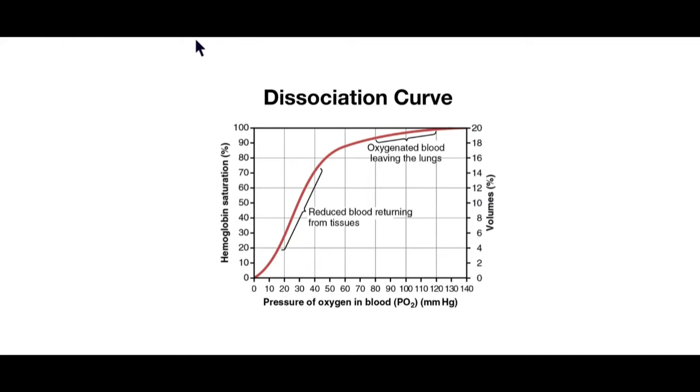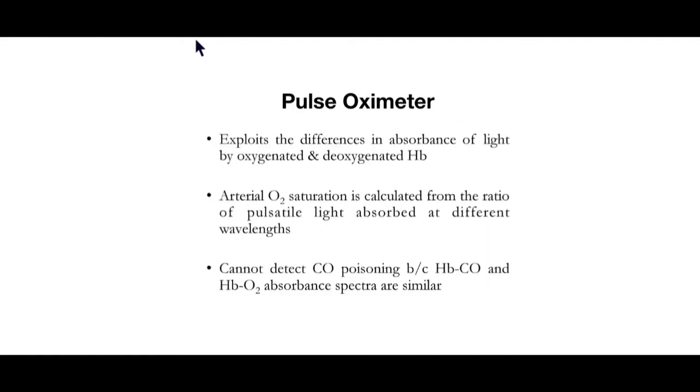All right, so our pulse oximeter. I'm sure you guys know what that is. You've seen that before. You put it on your finger or your toe, depending on how old you are. Kids usually have to have it put on their feet. But what it's really doing is looking at the oxygen content of pulsatile versus non-pulsatile blood. Why do we care about that? What's pulsatile blood? Where the circulation is at? Arterial, right?